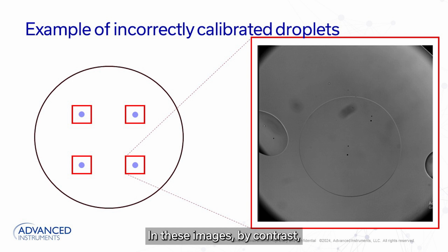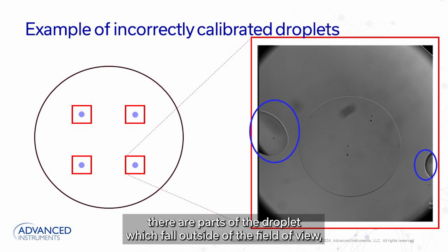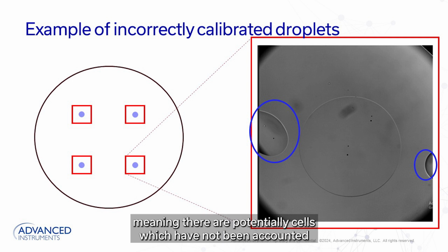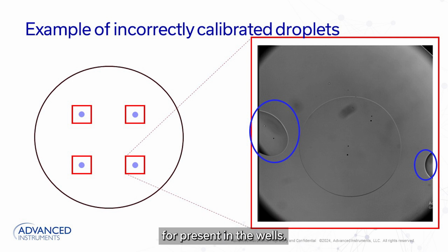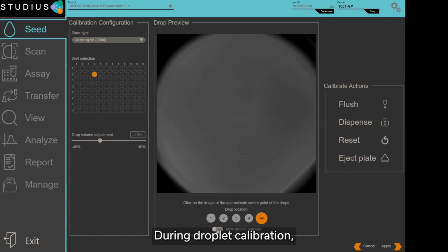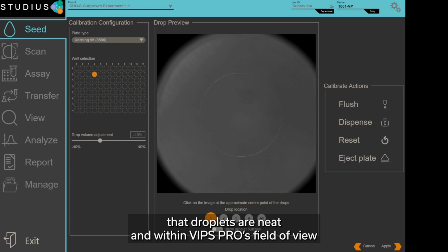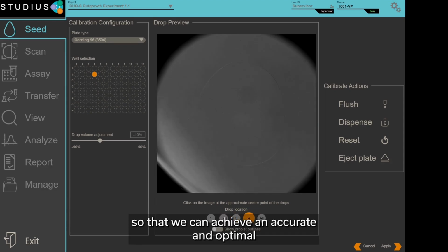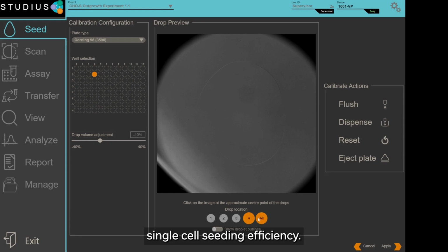In these images, by contrast, you can see that there are parts of the droplet which fall outside of the field of view, meaning there are potentially cells which have not been accounted for present in the wells. During droplet calibration, our objective is to ensure that droplets are neat and within VIPS Pro's field of view so that we can achieve an accurate and optimal single cell seeding efficiency.